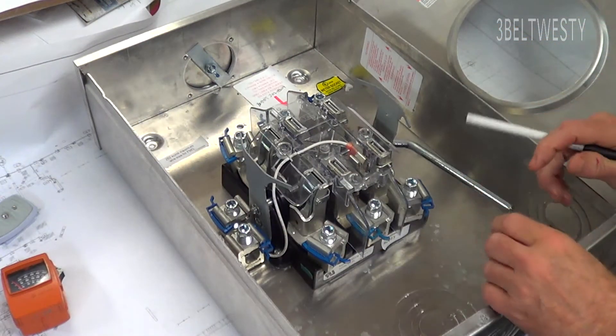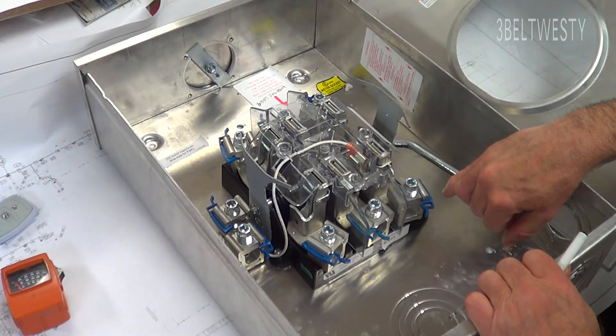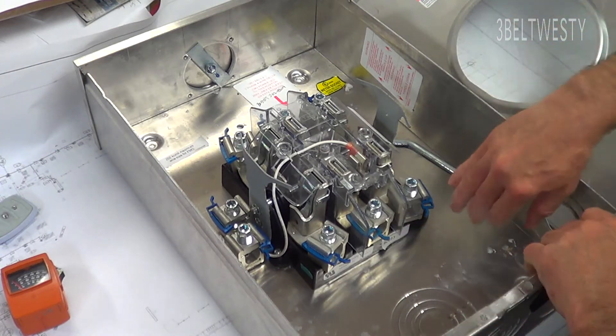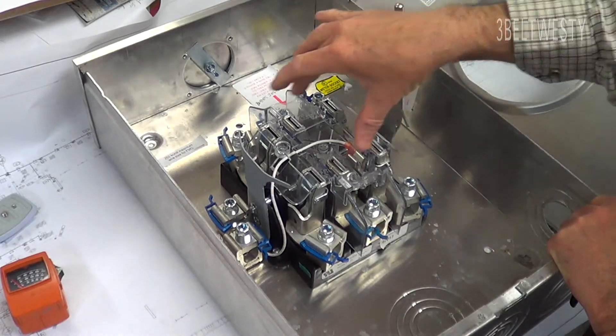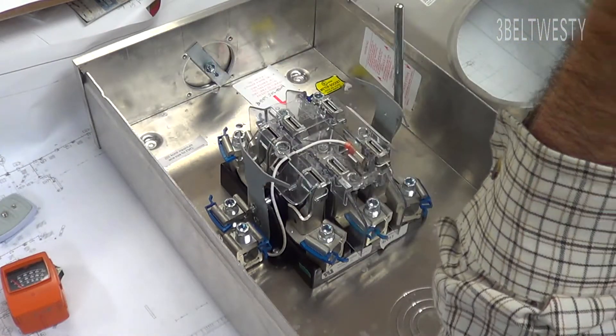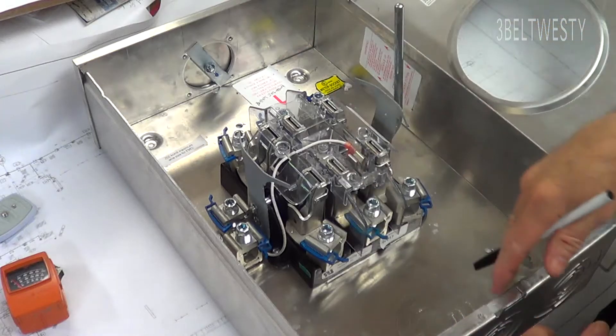This is the bypass. It's used so before the meter man pulls the meter, he goes through and pulls this over, and that shorts the lugs together. Then he can pull the meter out and there's still power going to the customer - you don't interrupt the power if you have to swap the meter out.